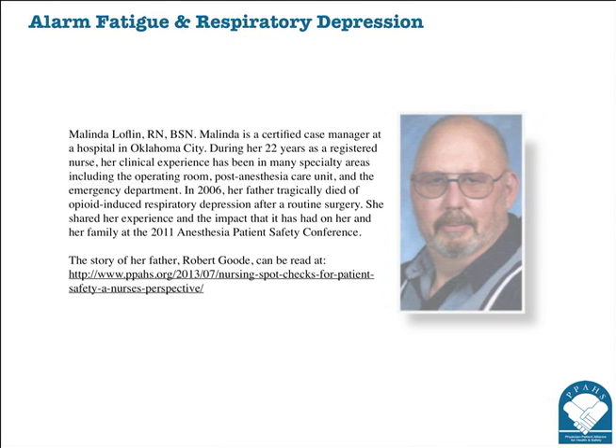On the pulse oximetry in particular, when it comes to respiratory depression, that alarm doesn't have a different sound for whether the patient pulled the probe off, is moving, or is literally having an issue. You take a ward with, say, 20 rooms, and 20 pulse oximetry devices going at the same time — you get so used to hearing those that you don't respond until you realize that alarm isn't silencing itself. But by that time, you could have gotten beyond the threshold point of being able to bring that patient back safely.